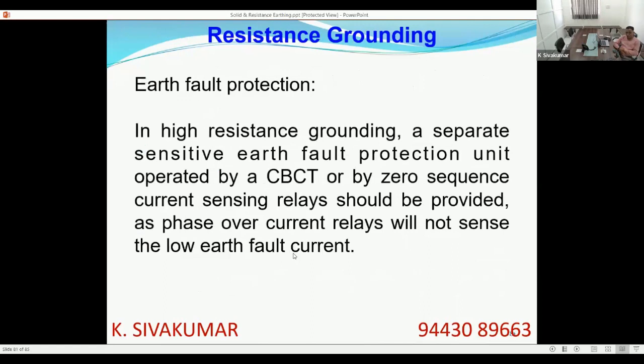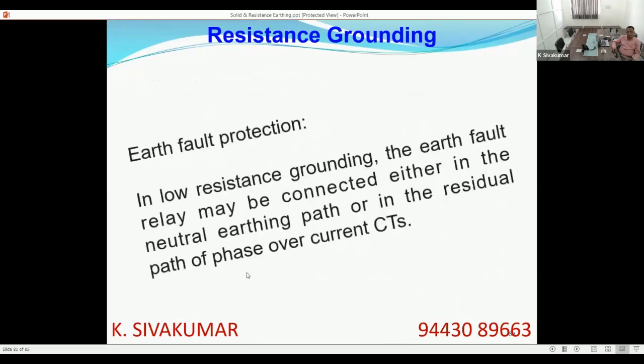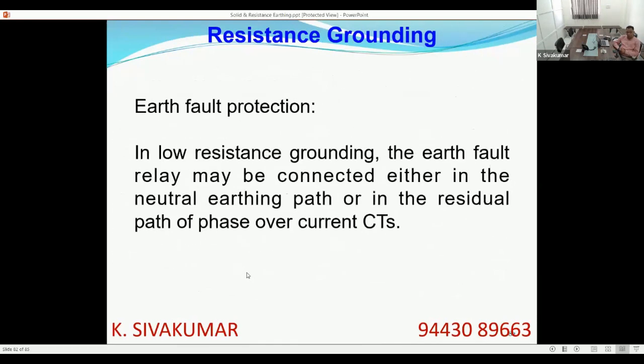Protection. In high resistance grounding, a separate sensitive earth fault protection unit operated by a CBCT or by a zero sequence current sensing relay should be provided, as the phase relays will not sense low earth fault current. In low resistance grounding, the earth fault relay may be connected either in the neutral earthing path or in the residual circuit of the phase over current CTs. We have seen both. So it is quite simple, possible to detect and isolate.